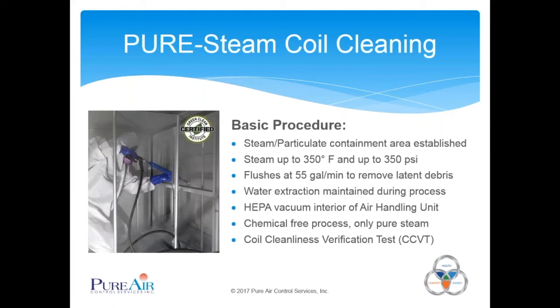We always do a CCVT test, a coil cleanliness verification test, to demonstrate the difference before and after the procedure. We take readings across the coils, especially the big ones. Our work order has a map of the coil with different reading points, and we take readings before and after at each spot to see where the most fouling is occurring and where we have to work hardest to loosen and remove it.